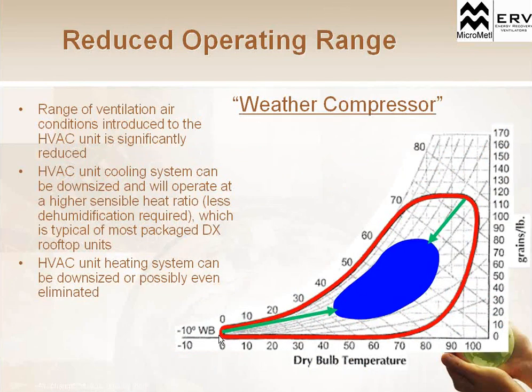If we look at this diagram here on a psychrometric chart, this red outlined area is the normal temperature and humidity variations that we would see from outside air in our climate zone, right? 0 degrees, -10, all the way up to maybe 100, a little over 100 degrees. So this is the outside air that we would normally see coming into our rooftop unit. With an energy recovery ventilator, we have reduced that temperature range, that humidity range, to this blue bubble.